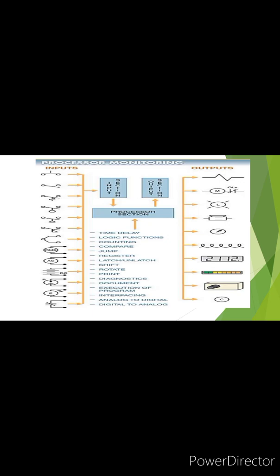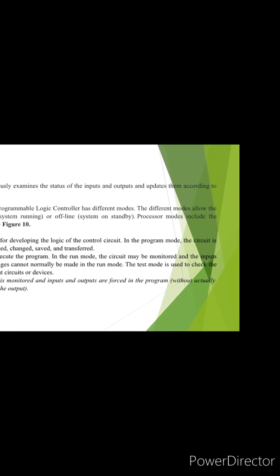This is Figure 9. Processor monitors inputs, input section, and output section. Output. Processor section. Time delay, logic functions, counting, compare, jump, register, latch, unlatch, shift, rotate, print, diagnostics, document, execution of program, interfacing, analog to digital, digital to analog, the status of the inputs and outputs and updates them according to the program. The processor section of a programmable logic controller has different modes. The different modes allow the controller to be taken online, system running, or offline, system on standby.